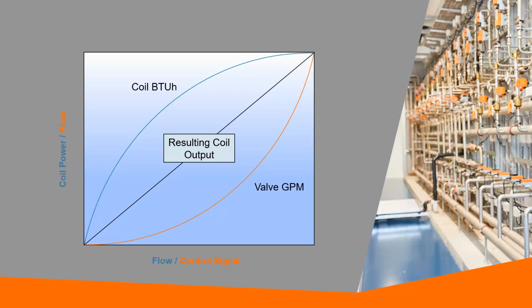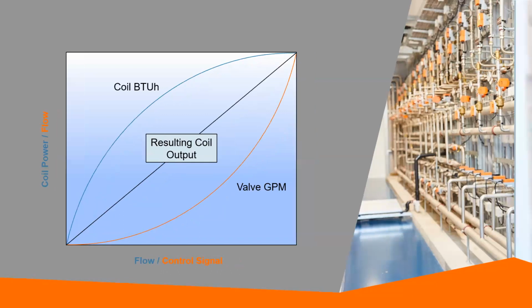The idea is that with a properly sized valve and coil, that linear result will occur when plotting the control command versus the coil output, essentially canceling each other out. And that's where that linear line comes from. So when we size pressure dependent valves, we use this formula. This is the flow coefficient formula that many of us are familiar with. This formula shows that flow will vary by the square root of the pressure drop.